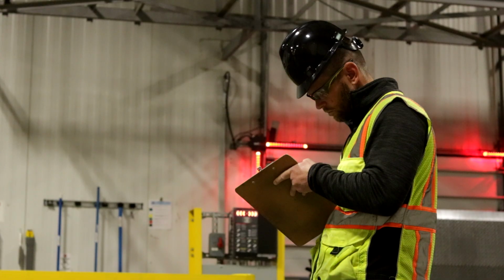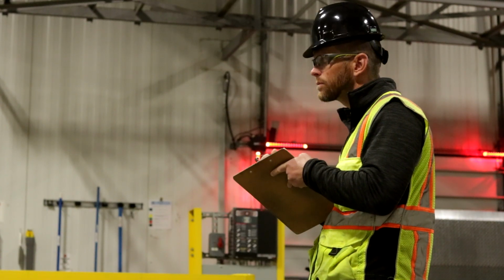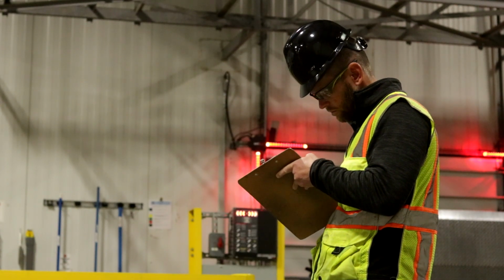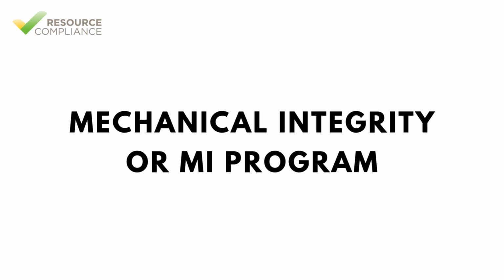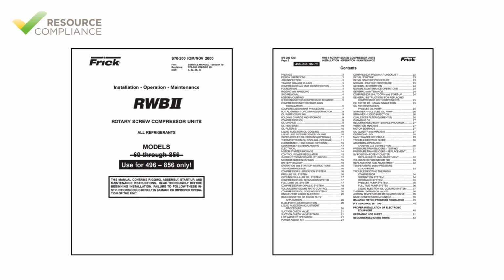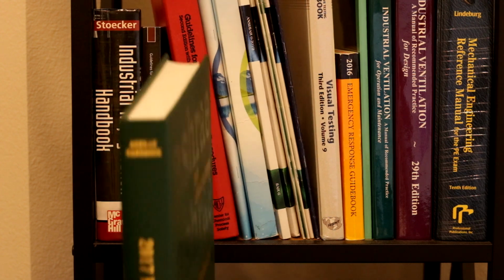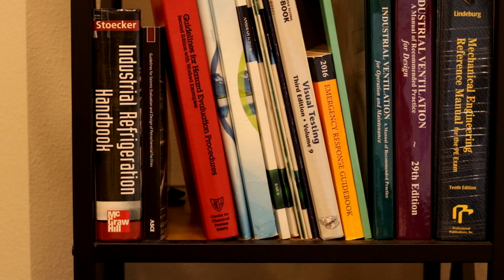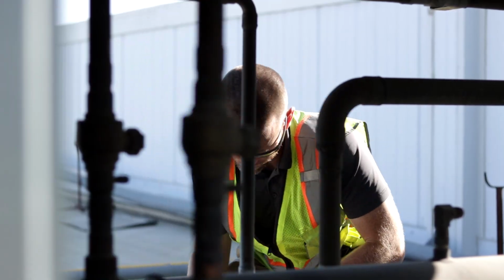For ammonia refrigeration systems, the RMP and PSM regulations mandate that owners implement a mechanical integrity or MI program. Typically, the MI program will be designed to address the inspection, testing, and maintenance, or ITM tasks that are required by the following: the equipment manufacturer, recognized and generally accepted good engineering practices, or RAGAGEP, and prior operating experience.